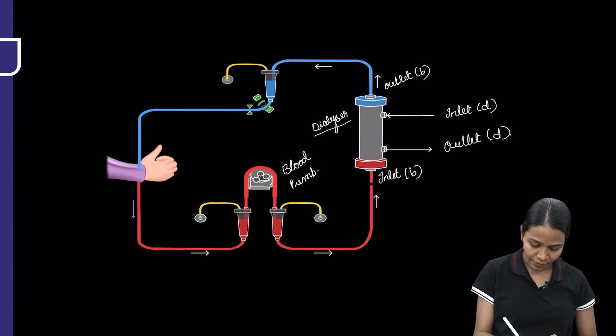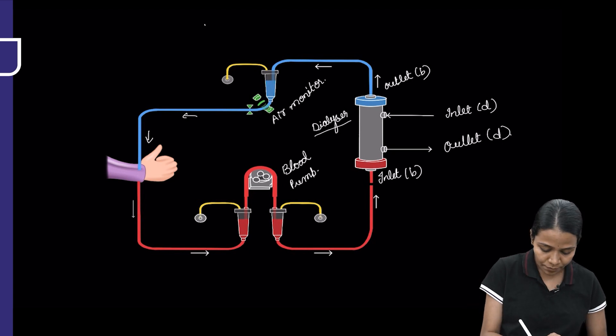It comes into the arterial line and then goes into the blood pump. From there it enters into the dialyser. This is the inlet for the blood and this is the outlet for the blood. This is the inlet for the dialysate and outlet for the dialysate. Then it goes into the venous chamber. Here it will have an air monitor, because if air is there, the blood cannot be returned back into the body. Then the blood goes back into the body. This is the blood circuit.